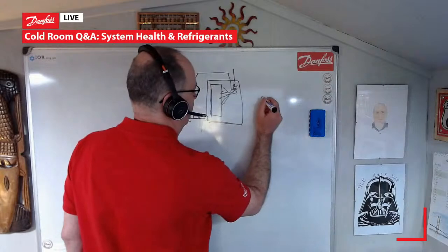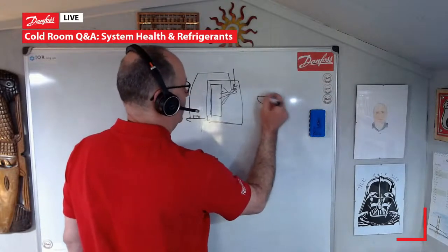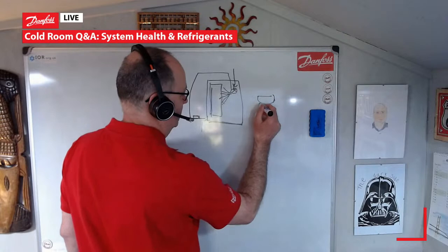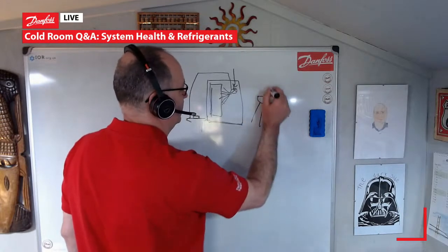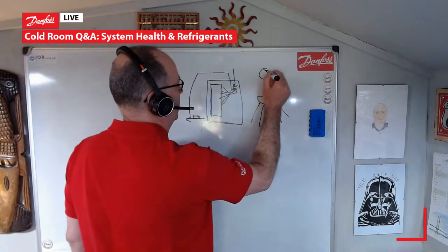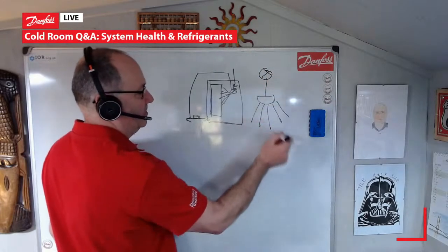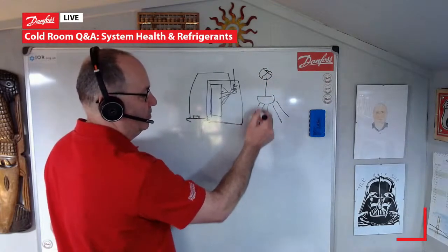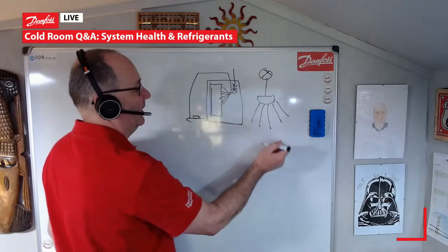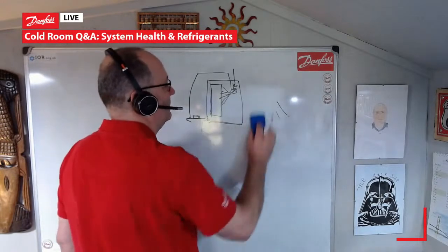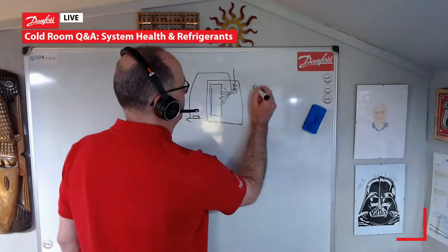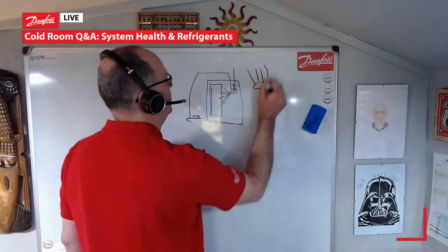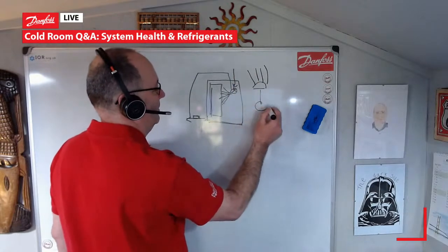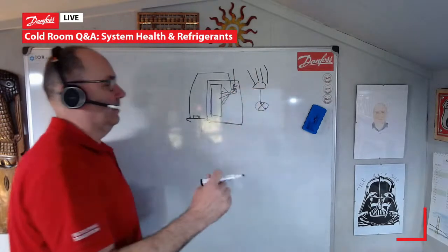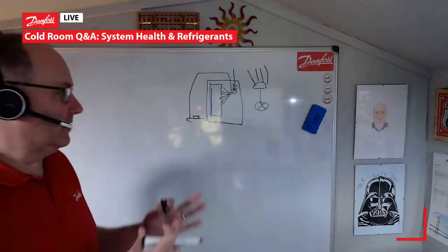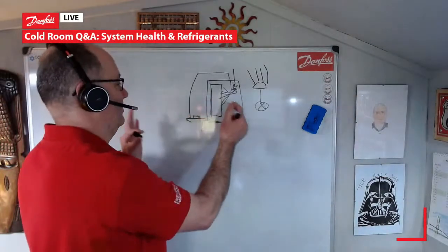If we talk about our distributor, let's do it that way. So that's our distributor, liquid feeding in from our expansion valve. If the distributor's pointing downwards, we get very good liquid distribution in all the distributor leads. In a lot of cases, you'll see the distributor is basically pointing upwards and then feeding into the coil. Not the greatest for liquid distribution. So get the basics right on the evaporator first.